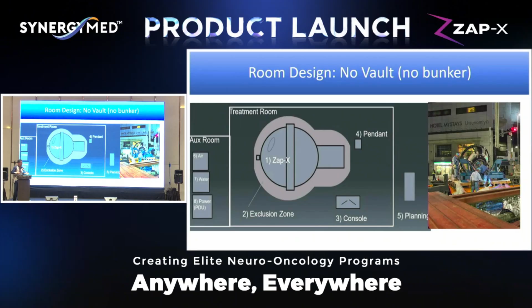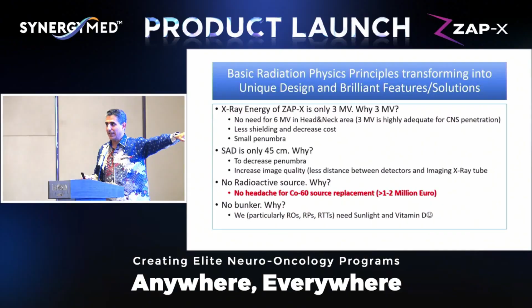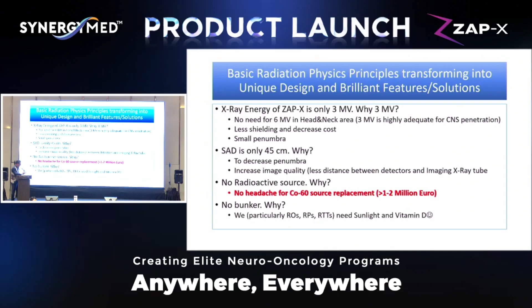Another issue is the red one, because the others are already mentioned. There is no headache of cobalt-60 source replacement. When the other vendor comes to me, I say that if you would like to be well balanced, please give HACETTEPE University an unlimited cobalt-60 source. Then you will be balanced during the tender. That's a basic thing I would like to say. As HACETTEPE University, we do not want to replace the cobalt-60 source every 6 to 7 years, costing at least 1 to 2 linear accelerators. That's another reality in terms of cost effectiveness.